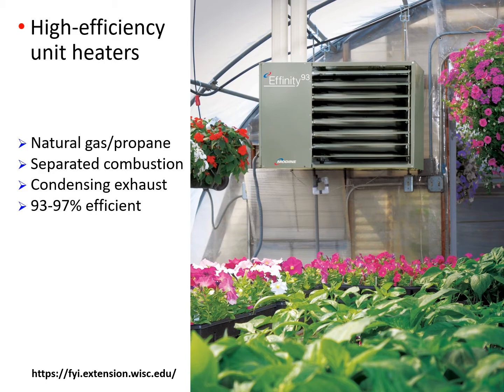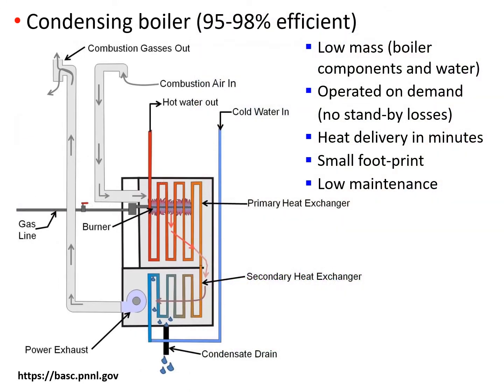In order to ensure that the air used for the combustion process does not contaminate the greenhouse environment, it is kept separate from the air inside the greenhouse. Note the two PVC pipes that deliver and remove air to and from the unit heater. Condensing boilers save energy by recovering heat energy from the water vapor that was produced during the fuel combustion process. Condensing the produced water vapor recovers heat that can be used to preheat water returning to the boiler. The conversion efficiency of condensing boilers is very high, often easily offsetting any increase in purchase price over just a few years of operation.